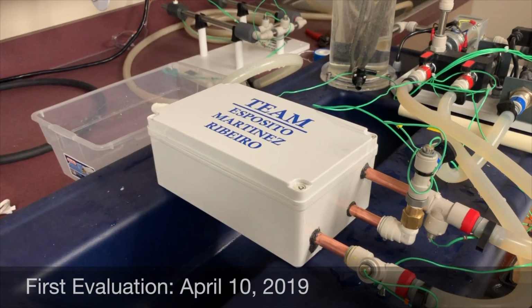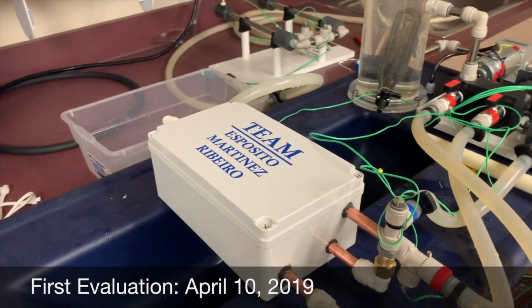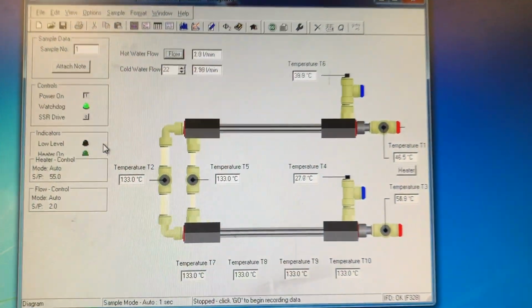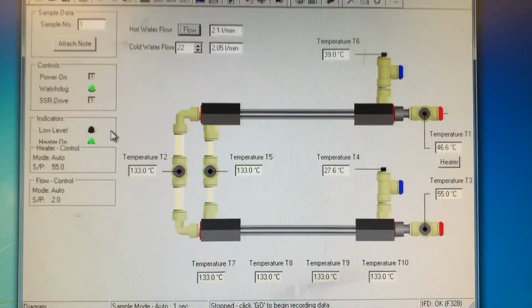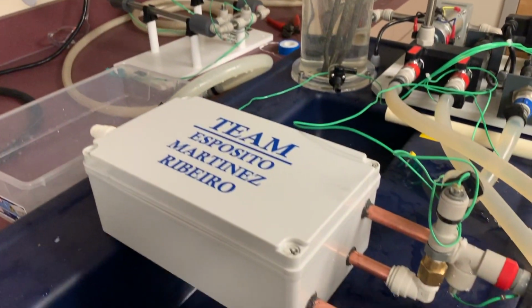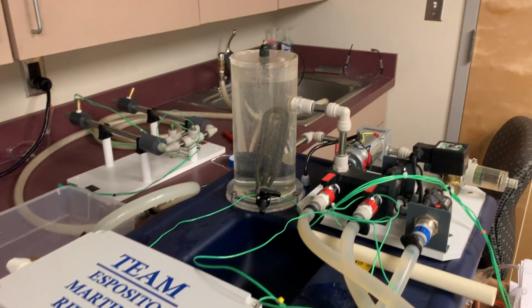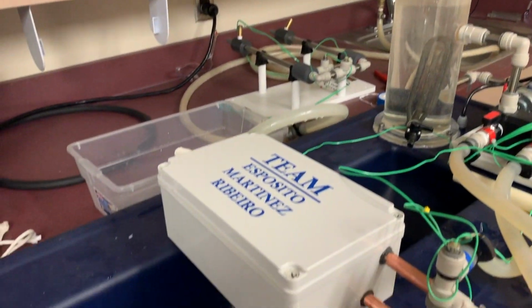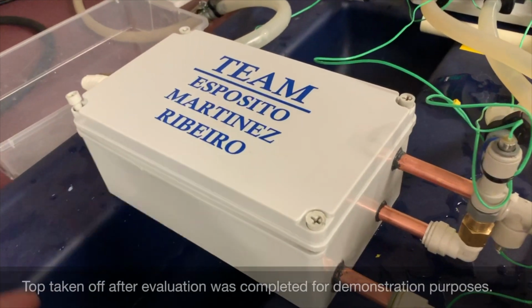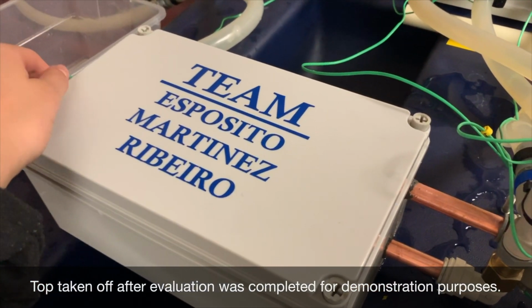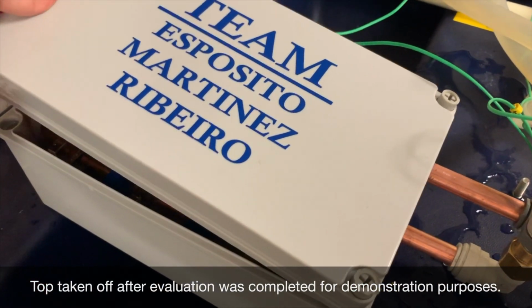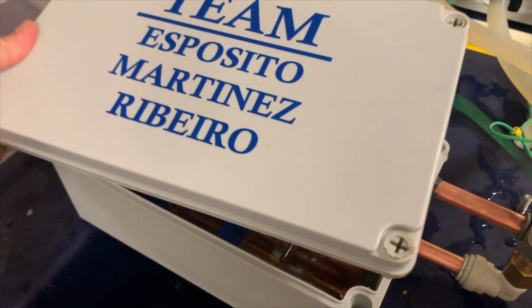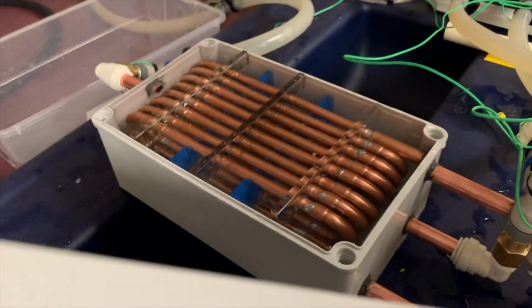The first evaluation was conducted on April 10, 2019. The heat exchanger connected properly at both inlets and outlets, and the epoxy held extremely well during the first evaluation. The hot water inlet temperature was 55.7 degrees Celsius, and the hot water outlet temperature was 46.5 degrees Celsius. The cold water inlet temperature was 27.5 degrees Celsius, and the cold water outlet temperature was 39.1 degrees Celsius.